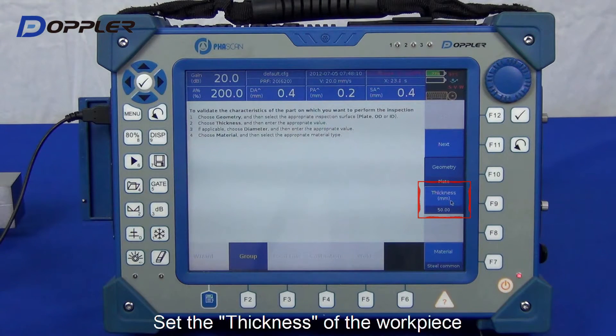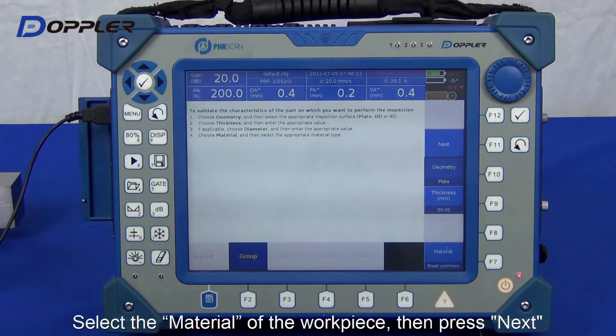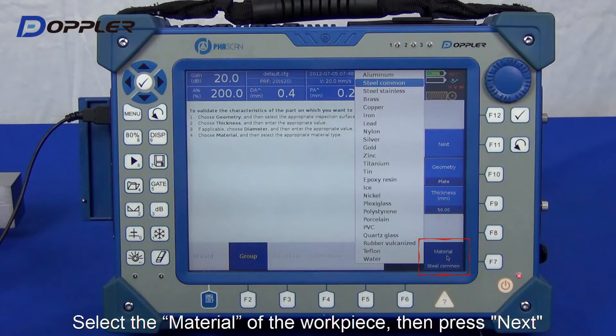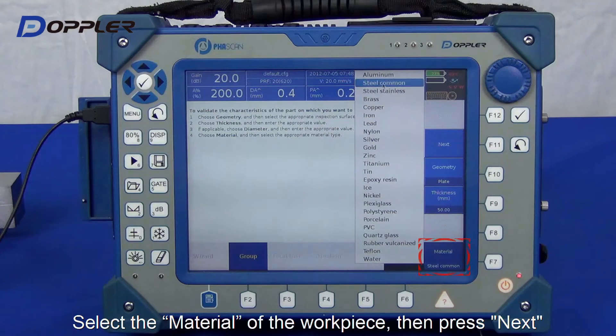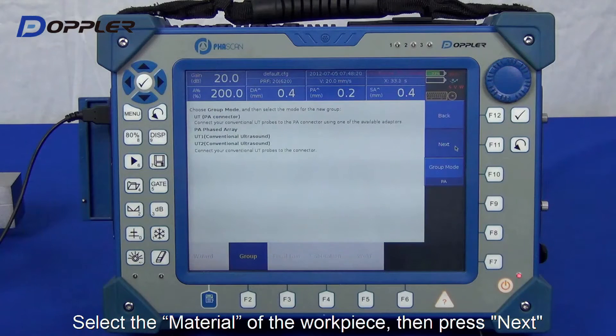Select the wedge type and the thickness of the specimen. Select the inspected material. For those materials unlisted, please input the velocity manually.